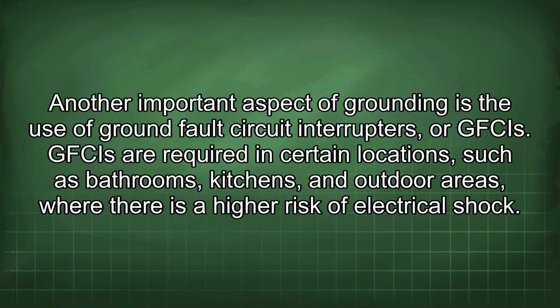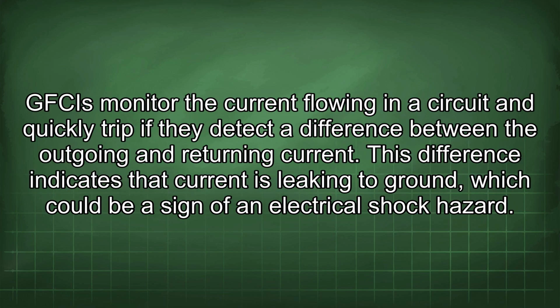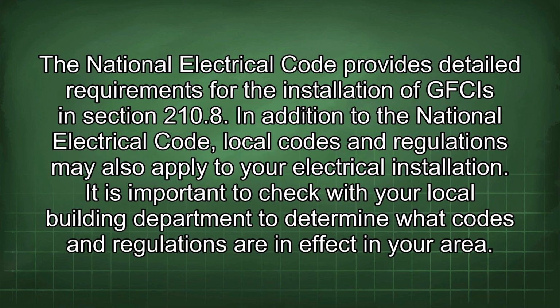Another important aspect of grounding is the use of ground fault circuit interrupters, or GFCIs. GFCIs are required in certain locations, such as bathrooms, kitchens, and outdoor areas, where there is a high risk of electrical shock. GFCIs monitor the current flowing in a circuit and quickly trip if they detect a difference between the outgoing and returning current. This difference indicates that current is leaking to ground, which could be a sign of an electrical shock hazard. The National Electrical Code provides detailed requirements for the installation of GFCIs in Section 210.8.